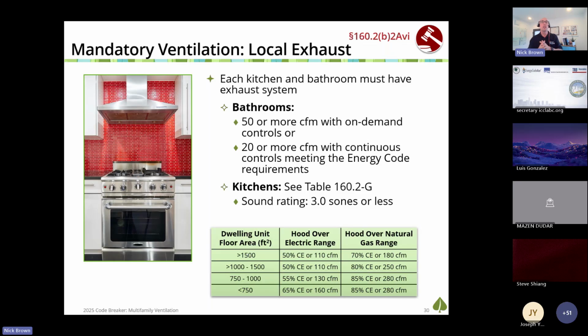I ran into this with my ADU. I put in a heat recovery ventilator, pulled 20 CFM out of the bathroom. That allowed me to vault the ceiling and not put in that bathroom exhaust fan. Kitchens have a local exhaust requirement as well. This table here, I don't see on enough plan sets. I think every architect should include this with a box around their dwelling unit and whether they're using electric or gas cooking, because it specifies the minimum airflow rate for your kitchen range vent hood. And notice it's higher for natural gas cooking and it's higher for smaller units, because those smaller units have higher concentration of the air pollutants, need to expel it more quickly.